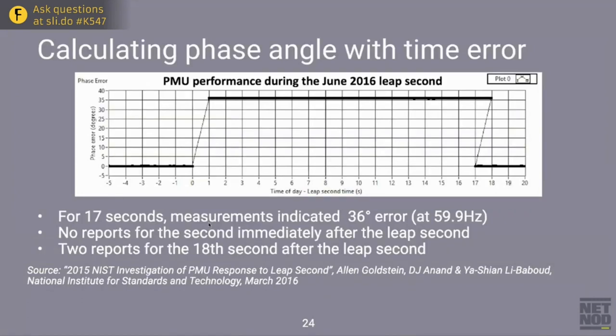Another thing they discovered was that the measurement equipment itself could not handle leap seconds. For 17 seconds there was in fact a 36-degree error at 59.9 Hz. There was no report for the second immediately after the leap second, and two reports for the 18th second after the leap second. This means that just after the leap second introduced in June 2016, no one really knew the state of the power grid in the US.